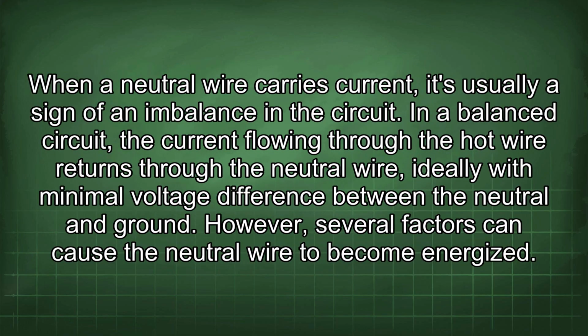When a neutral wire carries current, it's usually a sign of an imbalance in the circuit. In a balanced circuit, the current flowing through the hot wire returns through the neutral wire, ideally with minimal voltage difference between the neutral and ground. However, several factors can cause the neutral wire to become energized.